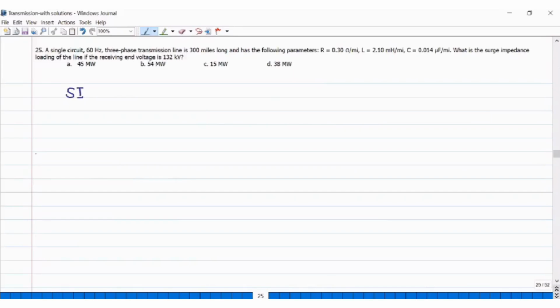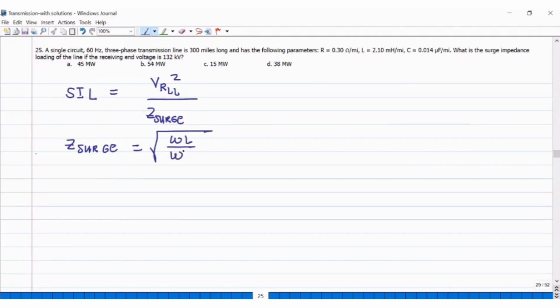The surge impedance loading is equal to VR line-to-line squared divided by the surge impedance. The surge impedance is equal to square root of omega L over omega C, or square root of L over C.